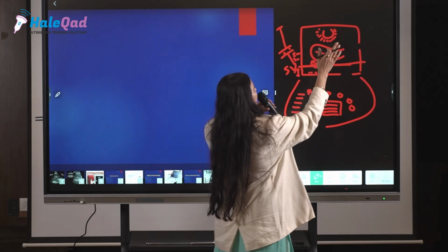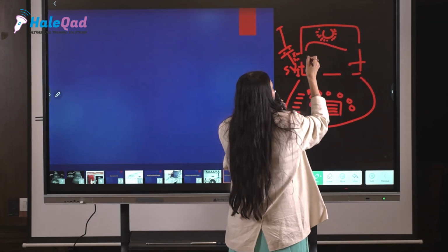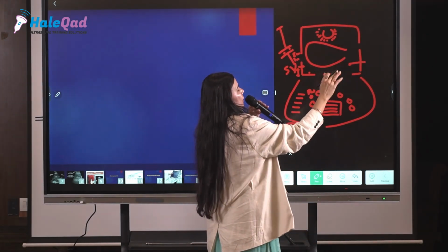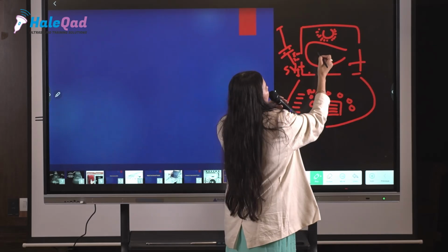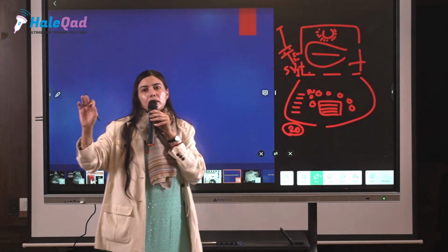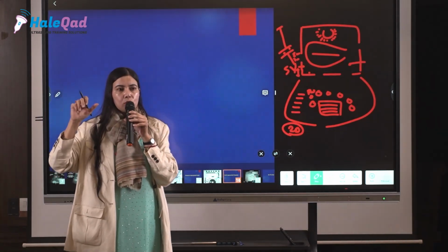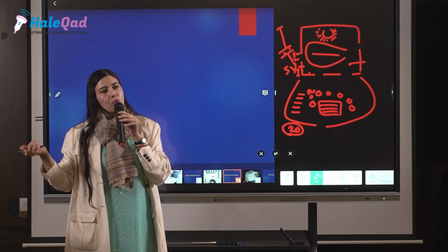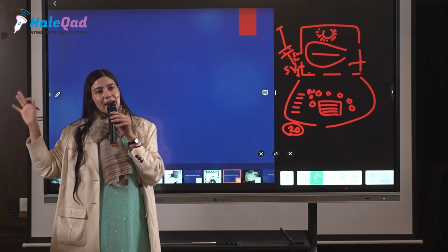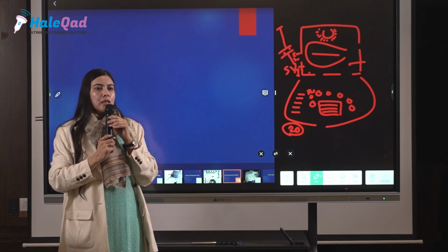So what you are going to see now, after adjusting the depth button, see, I made this area disappear by adjusting the depth, and the resolution is as such. Don't ever use the zoom button first. Whenever you are zooming the image, you are compromising the resolution. So the zoom option is the last button that we should go for. That is the last thing.